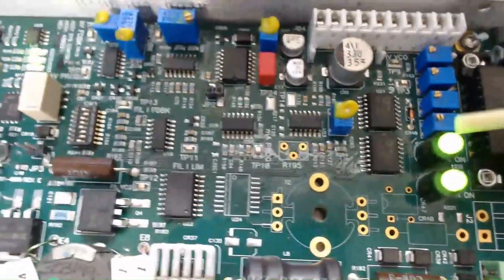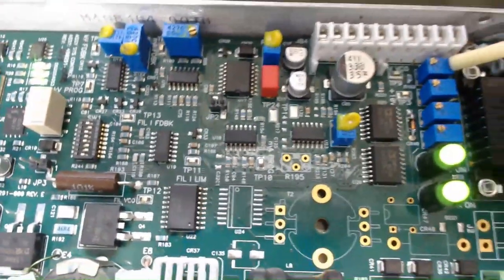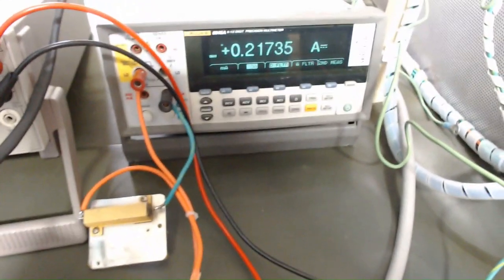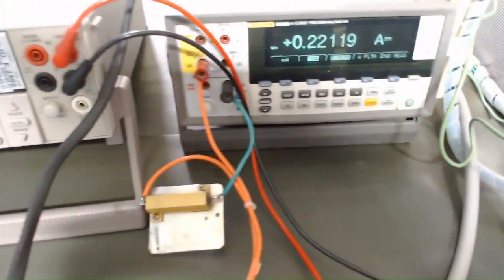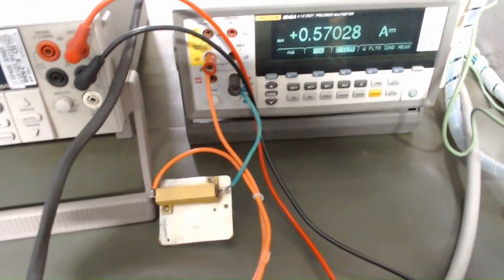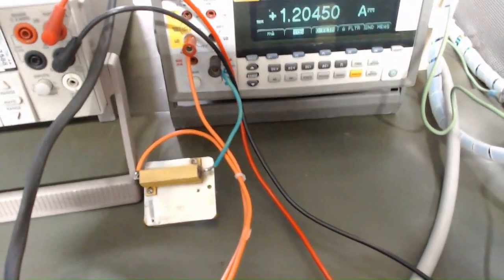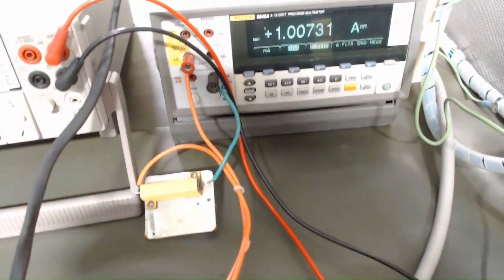The following tests are the filament limit and filament preheat range tests, using the adjustment potentiometers for filament preheat and filament limit. We will begin adjusting first the filament preheat pot between minimum and maximum value to ensure filament can be adjusted at least between 0.3 amperes and 1 ampere. In this case, as shown in the video, range should allow to adjust these values slightly lower than 0.3 amperes and slightly higher than 1 ampere in order to provide sufficient adjustment margin. This test is to be performed with the interlock open for the preheat to be active.